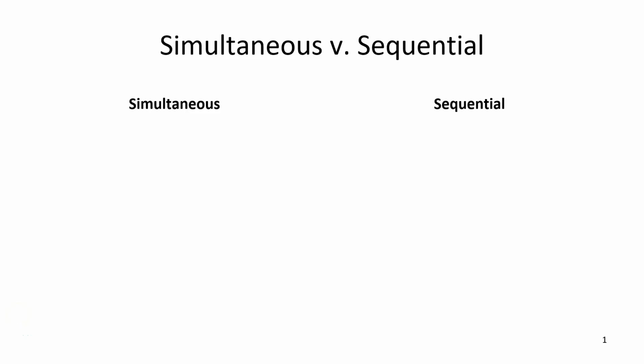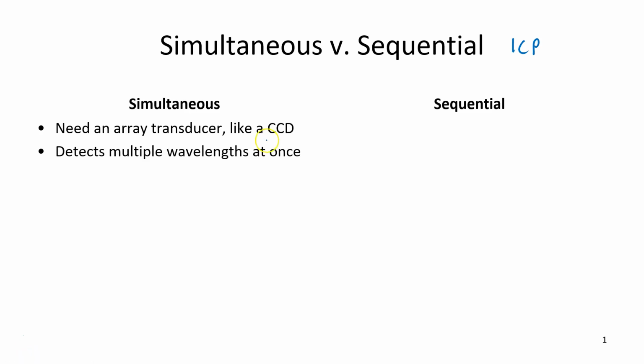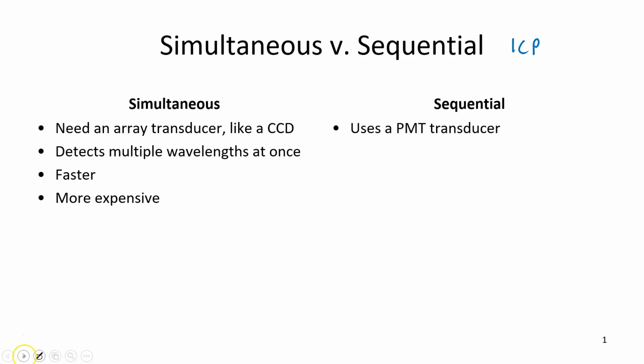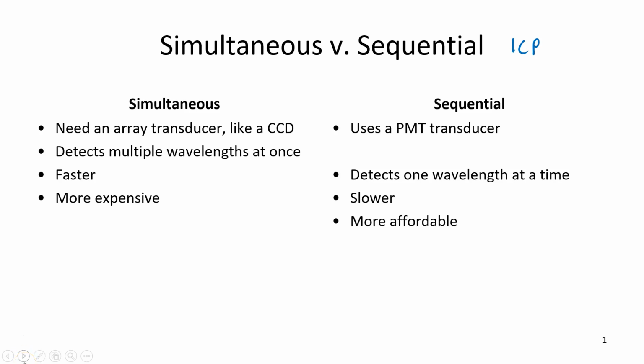Hi everyone. We're going to talk about the differences between simultaneous and sequential ICP instruments. So in a simultaneous instrument, you typically have an array transducer. Ours has that charge coupled device. And remember, the advantage of an array transducer is that it detects multiple wavelengths at once, making it faster and more expensive. In a sequential instrument, you don't have an array transducer. You probably have a PMT, meaning that it only detects one wavelength at a time, making it a little bit slower, but more affordable.